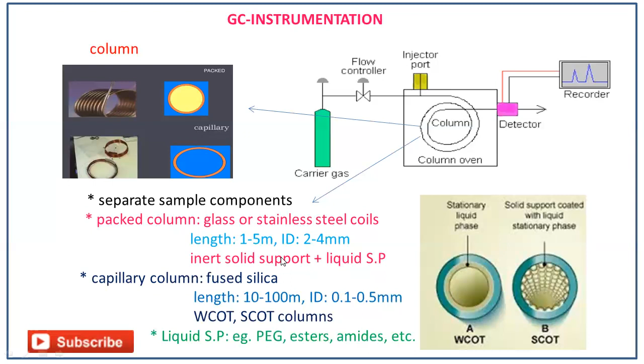So how do we know that the column is contaminated? Here we can see peak tailing in the final chromatogram, and sometimes we can also get ghost peaks. Additional peaks will also be present in the chromatogram. So these are the problems that we can see in the column. But how do we control this problem? We have to check the grade of the carrier gas, whether it is high grade or low grade, before starting the experiment. And we have to stick to SOPs, that is standard operating procedure. We have to do the equilibration process for a minimum of 12 hours, then we can clear this problem.